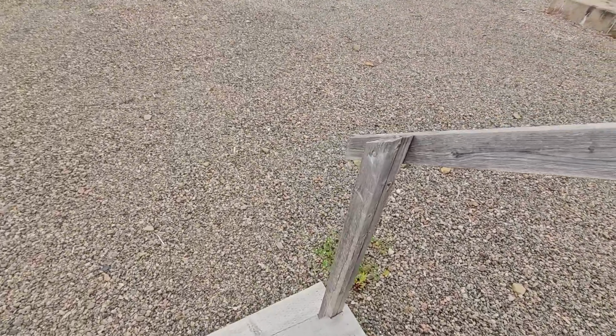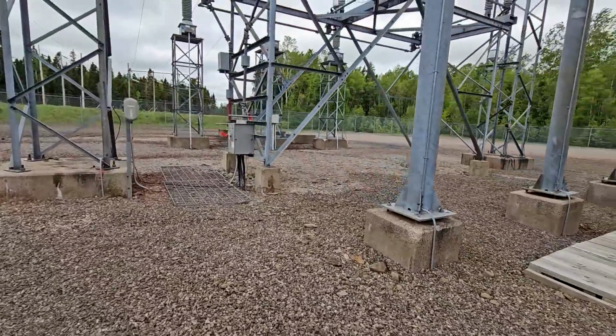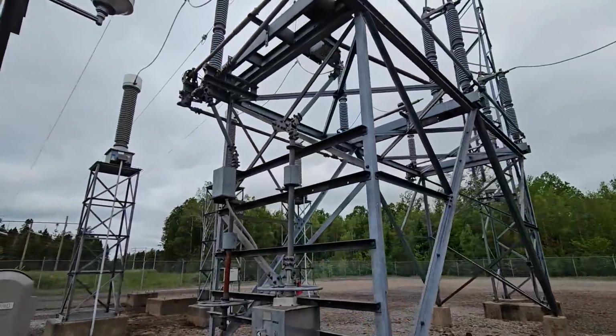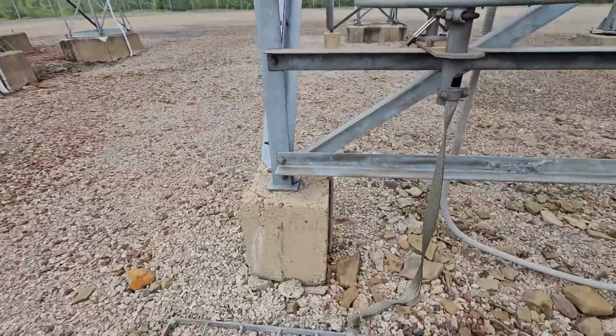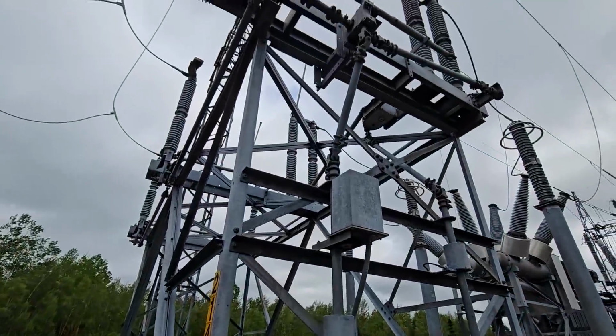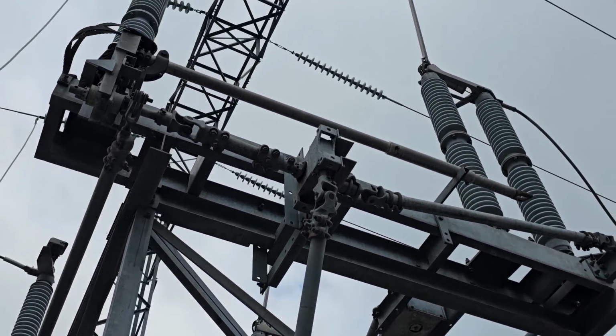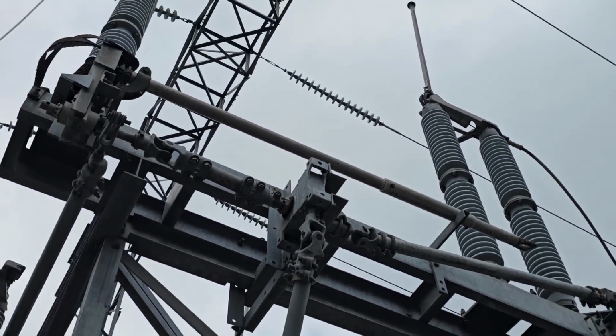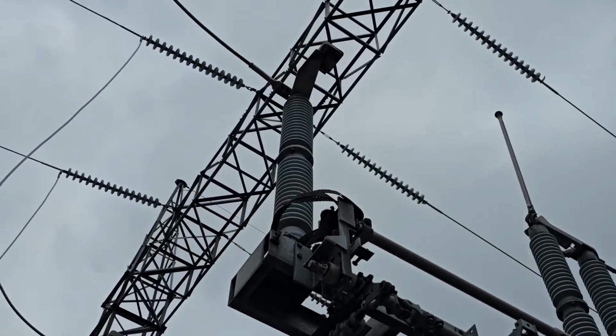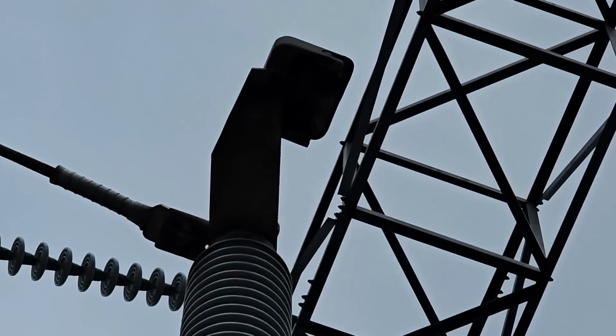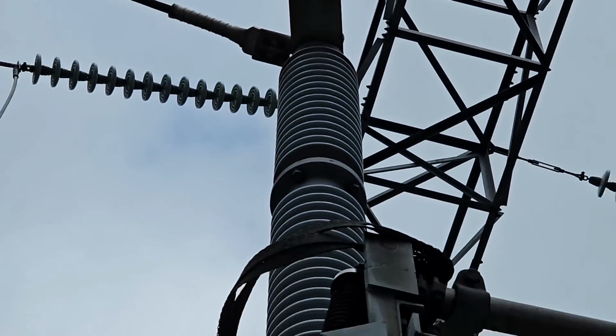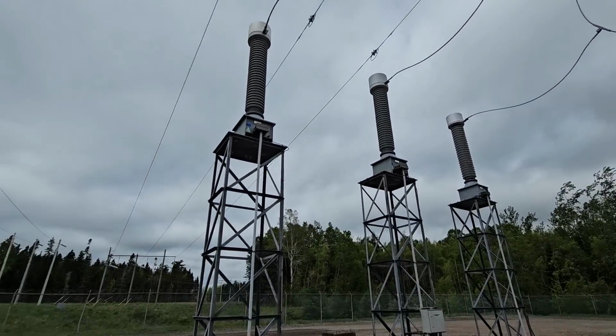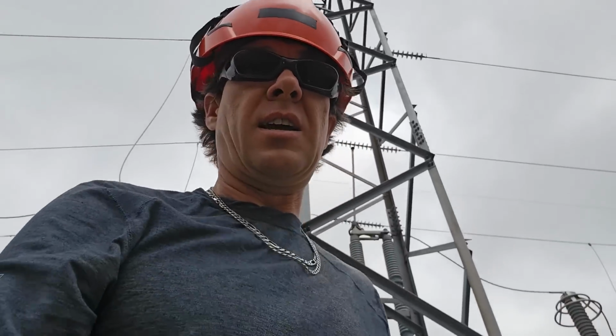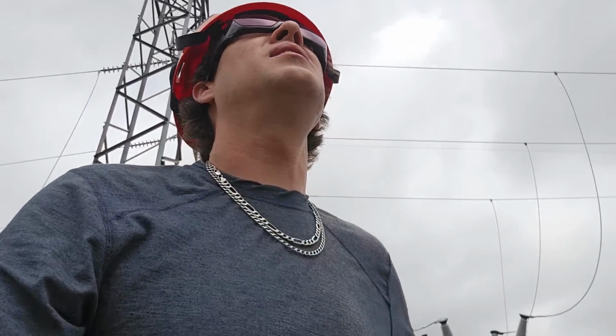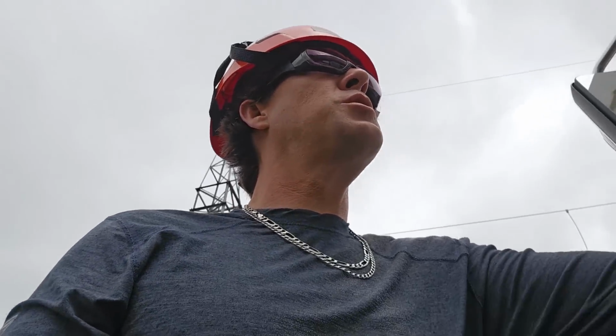Let's just take a closer look at the switch itself. So that's the ground switch we're going to be closing in, which is going to rotate that pipe, go through those universals, and this pipe right here, and it's really windy out. That's going to slide right up. It's too dark to get a clear shot. There is a connector inside that's going to ground that line out. That's pretty much it. So just standing by, waiting for the power system operator to call, and then I'll be able to complete my last step, closing in that ground switch.